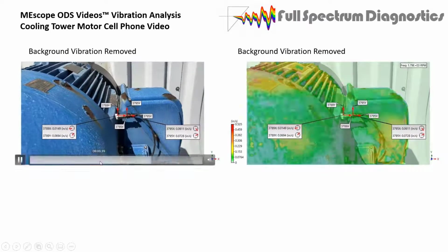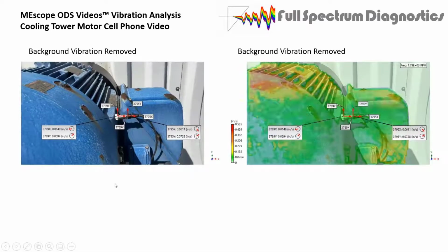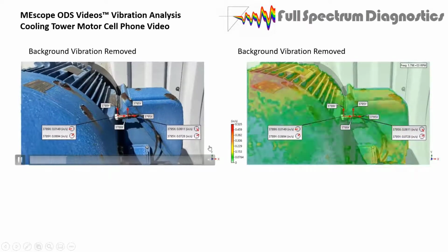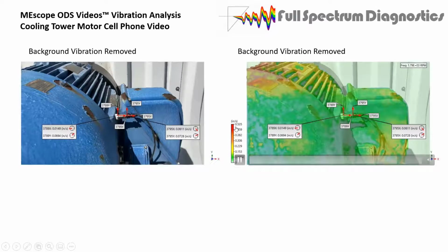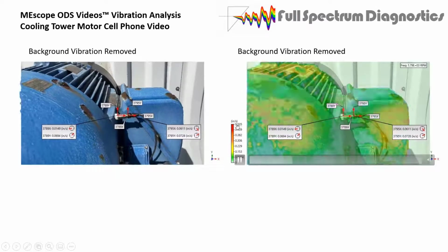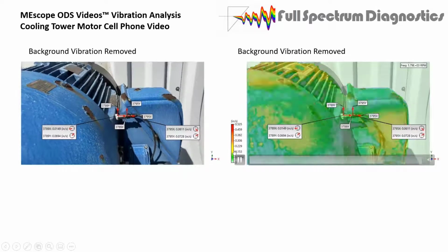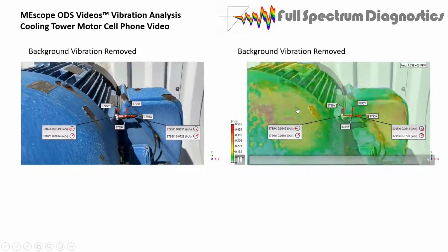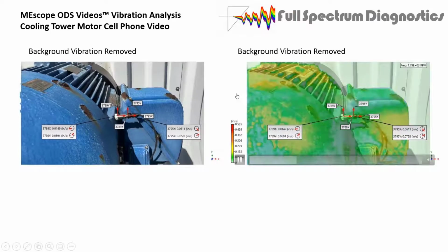0.5 was the 0.85 a couple of minutes ago. That was the average background vibration that got separated out. So it took it down about 30%, 30 to 40%, and now our highest levels are 0.535. So that's big for here. But this isn't what we're measuring for.